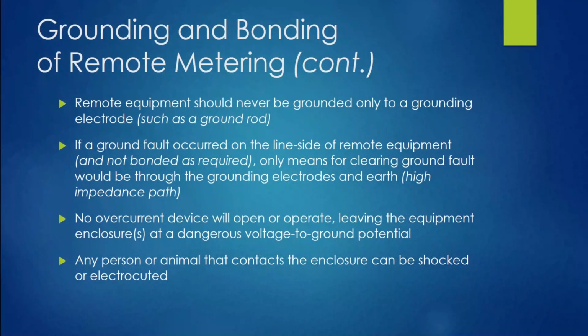I would prefer you not put one at the remote meter location. Not necessary. You're connecting to the grounding conductor within that remote meter, and we're going to see that here in a second in some examples. But I'm saying if you do put one, don't forget that you're required to do the one at the service equipment application, okay? That's the key. All right. Let's move on to the next portion.